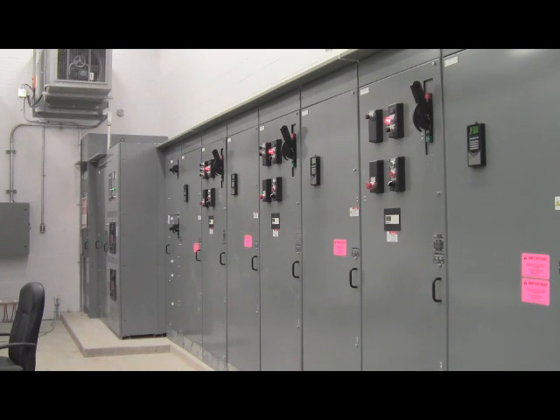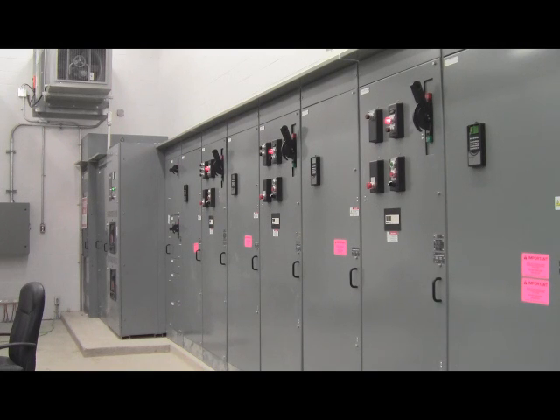Two pumps are active at all times, the primary and the secondary. The primary pump is what's going to take on the burden of all the work. The secondary just handles high level, which the odds are it will never reach. To compensate for the wear and tear on the pumps, we cycle them: pump A primary, pump B secondary, then pump B primary, pump C secondary, then pump C primary, pump D secondary, and so on. There's a regular cycle of times run. The sequence is based on hours run, not normal days.